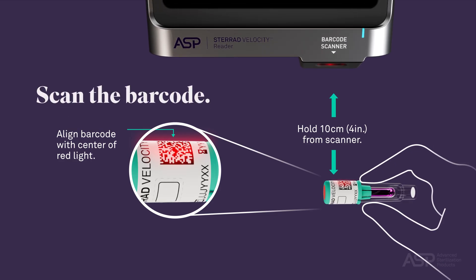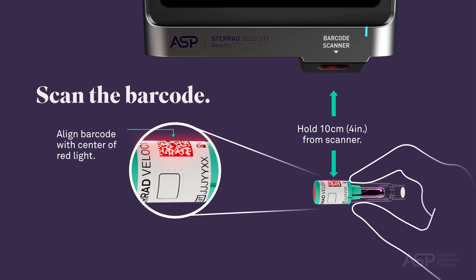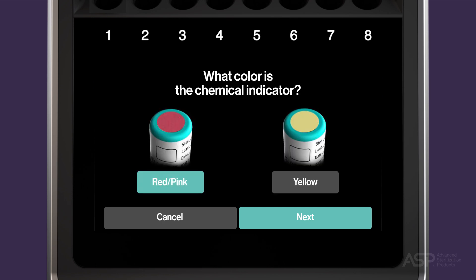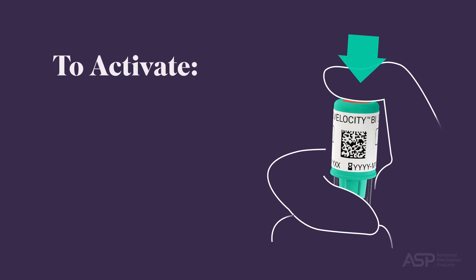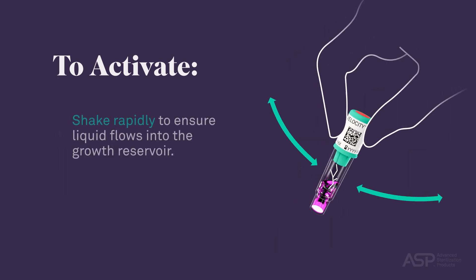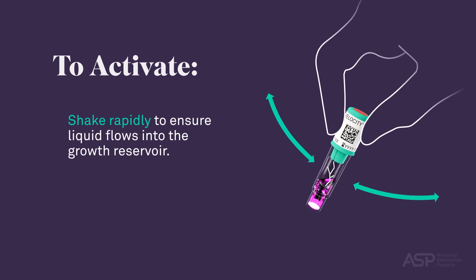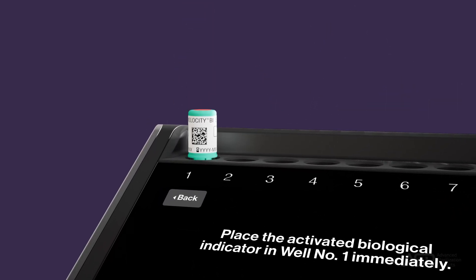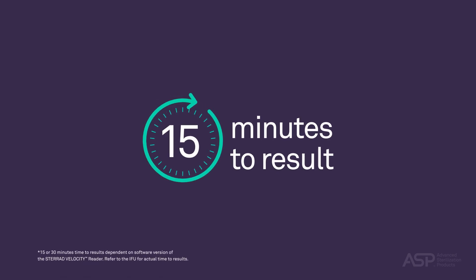When asked what type of BI PCD will be added, touch Control. Scan the barcode on the cap label using the barcode scanner on the front of the reader, then enter the operator's name or select from the list. If configured, an optional screen prompt will ask the operator to visually confirm the color of the chemical indicator on the cap. Activate the BI PCD by completely pressing the cap down until the glass ampule breaks; visually inspect to confirm it has broken. Shake rapidly to ensure liquid flows into the growth reservoir. Place the Control BI PCD in the selected reader well. Test results will be available in as fast as 15 minutes. A new positive control should be performed at least once every 24 hours using a BI PCD from the same lot as the test indicator.